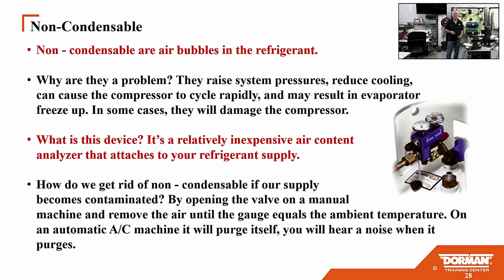How do we get rid of it? Opening the valve on a manual machine, remove the air until the gauge equals ambient. On my older machine, I had to hit a purge and everything else.